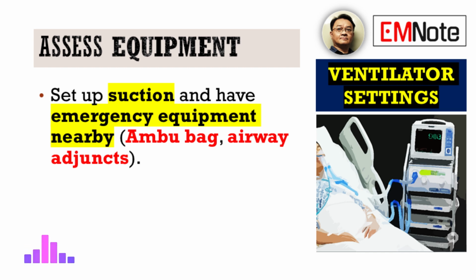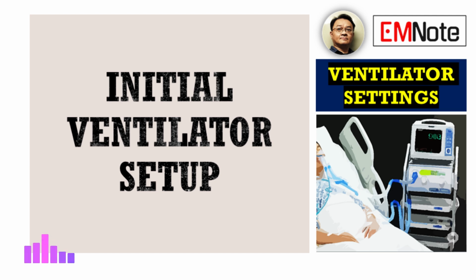Right. So with all those pre-checks ticked off, what are the first hands-on steps with the ventilator itself? It's time to bring the machine to life and assemble its components so it's ready to actually deliver those breaths. Exactly. The power-up sequence and the precise assembly of the breathing circuit are foundational here. Any misstep at this stage can compromise the entire process of ventilation and, crucially, the patient's safety. These are the critical building blocks before you even think about the actual patient connection.